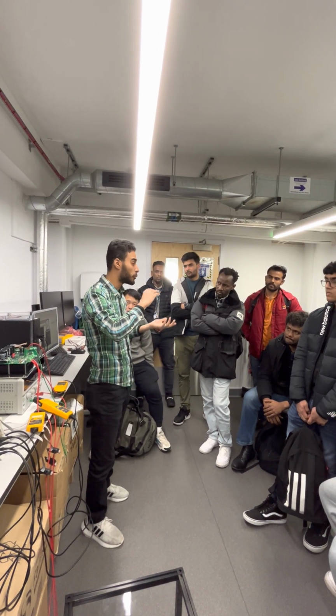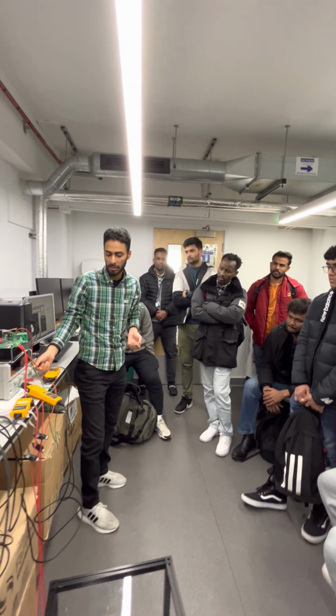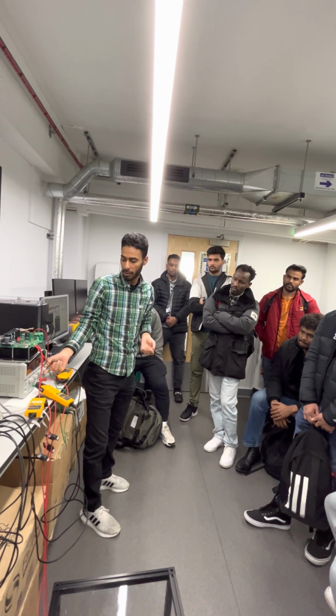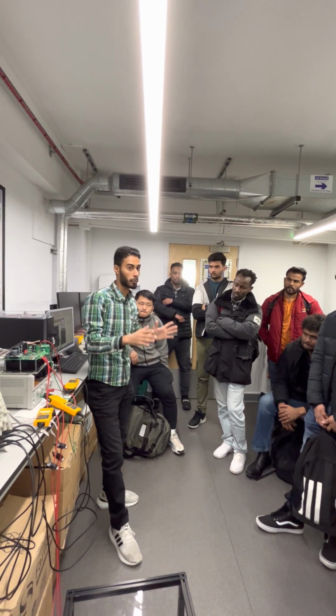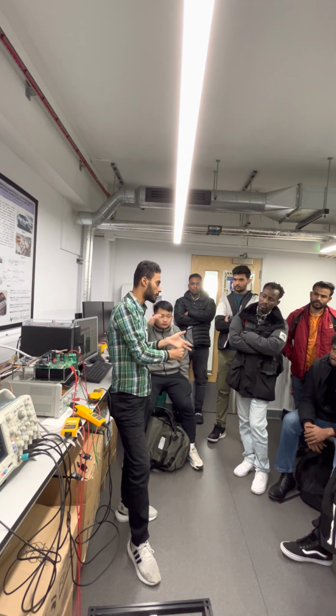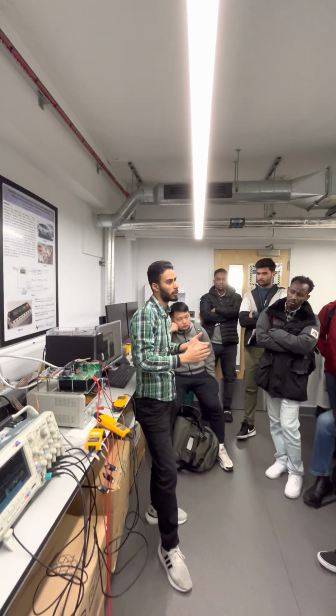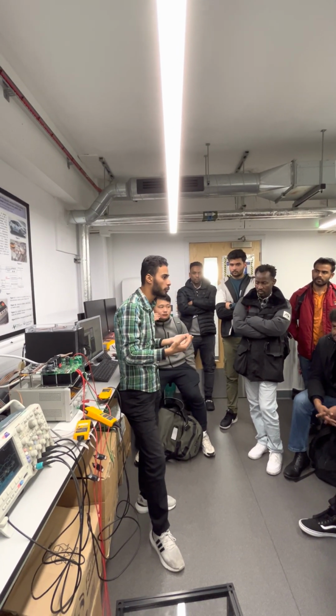So the ratio between the voltage and the frequency should be constant. If we reduce the voltage a little bit, this noise will disappear. So your controller should take care of the desired voltage and the frequency to operate in a smooth and efficient way, because we need an efficient control to reduce losses as much as we can.